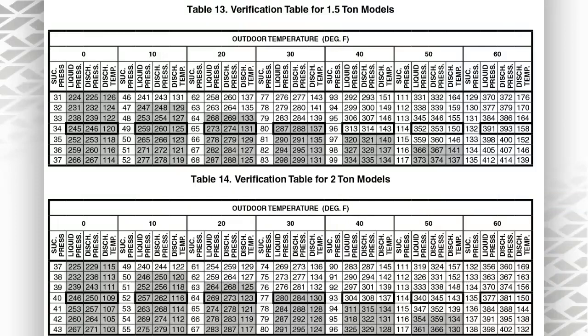I mean, there's other things that can affect it too, such as the evaporator fan motor on the outdoor unit not running. That's where you're in heating mode, the outdoor unit's running, the evaporator fan's not running. So the thing's just going to frost up and freeze over really quickly because you don't have any air being pulled through the coil. So that's one example of where you would get low discharge temperature. So keep that in mind when you're checking the charge on any heat pump system. Before you make any charge adjustments, you need to know and be using the manufacturer's charging chart.